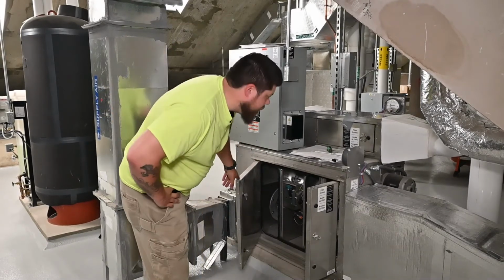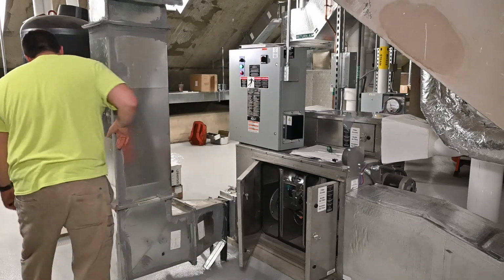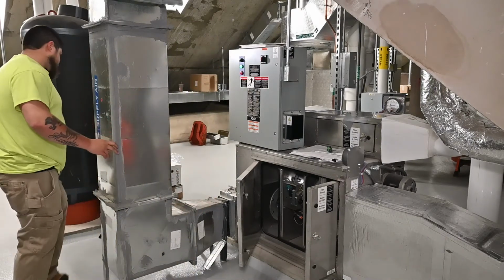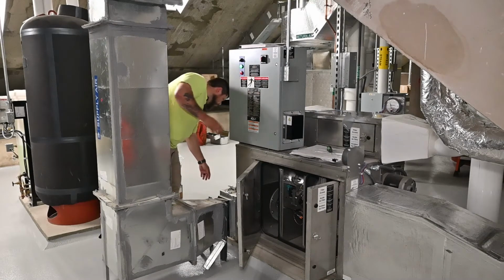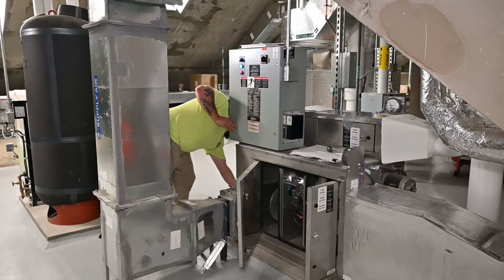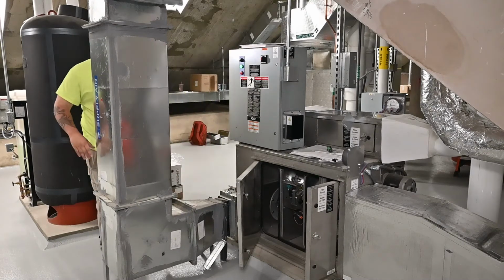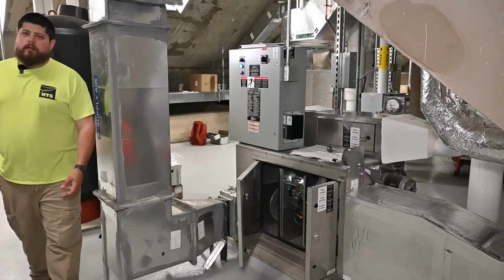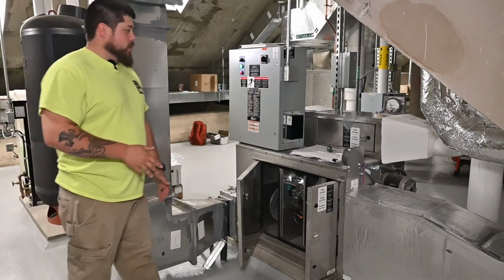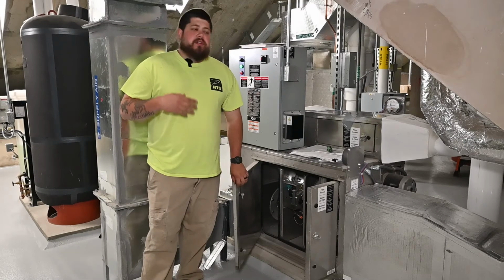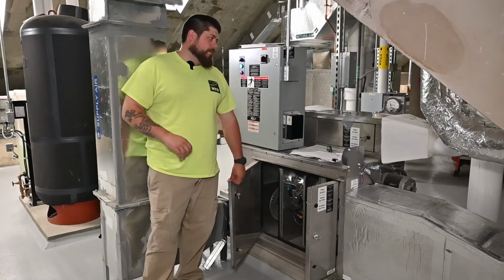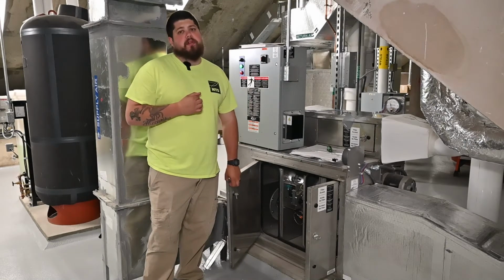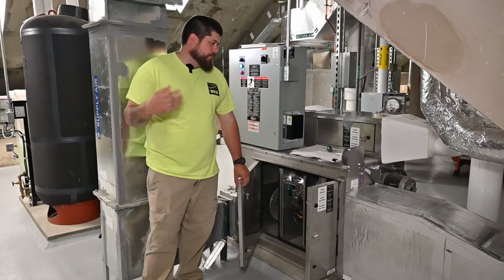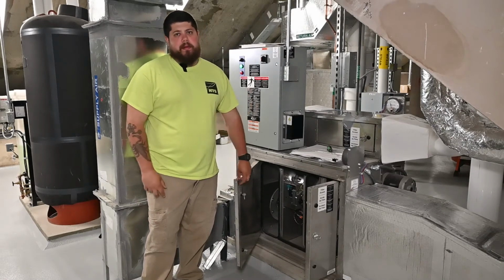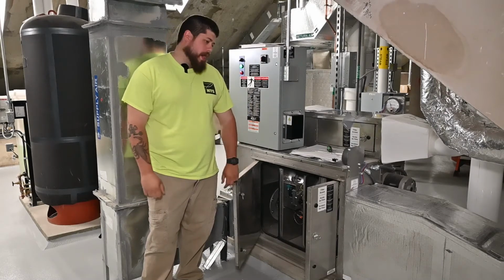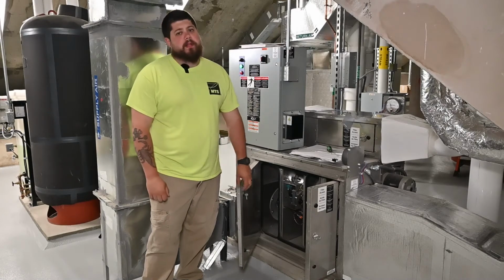I don't believe these motors... Oh, they do. Oh, no, they don't. So these motors here, the direct drive motors, do not have grease spots. They're internally greased because they're below a certain limit on sizing, so you do not need to grease them. Nothing should have to get done to these motors. I can tell they're a little dirty. If they collect dust or anything, compressed air on it wouldn't hurt, to keep it from getting inside the windings, but other than that, it should be good.